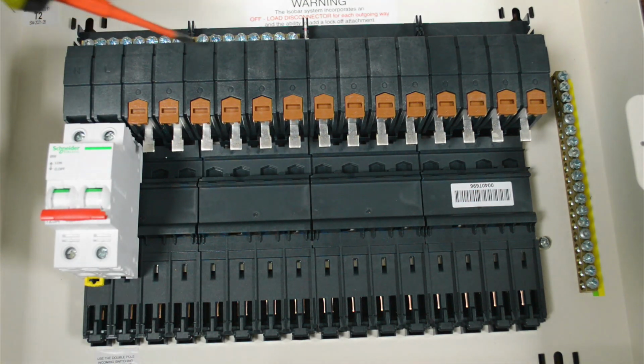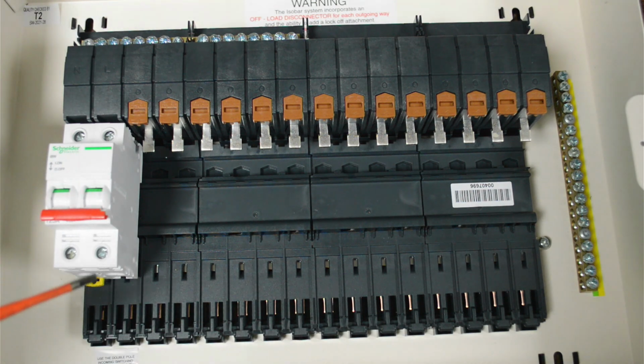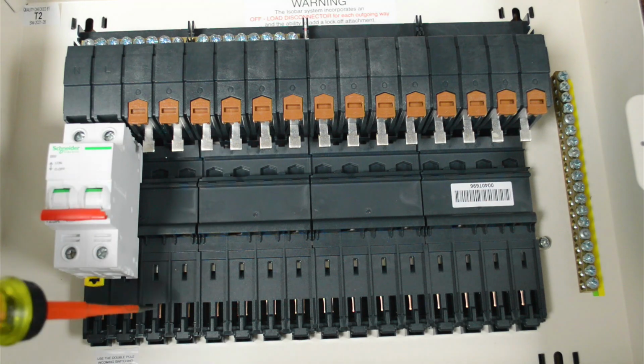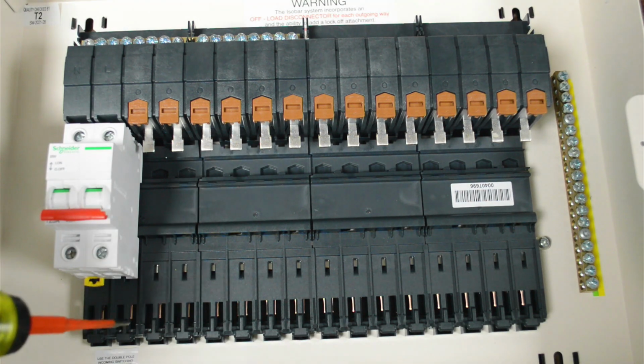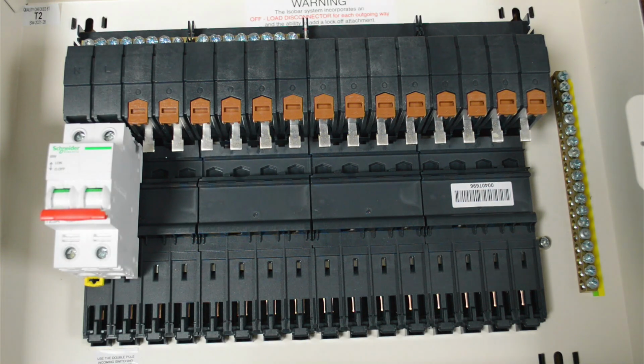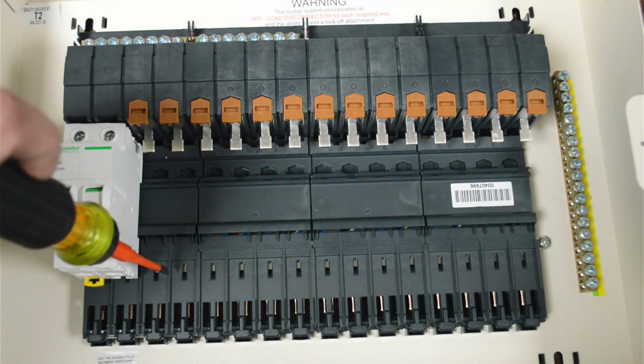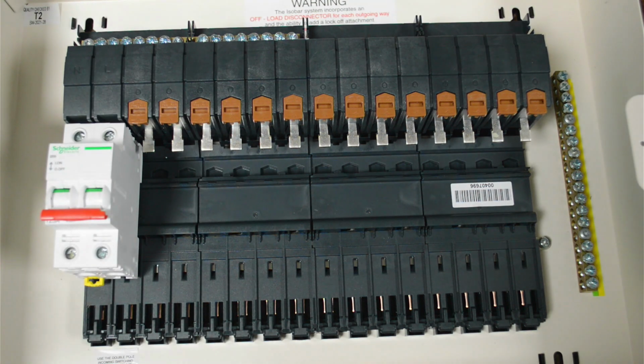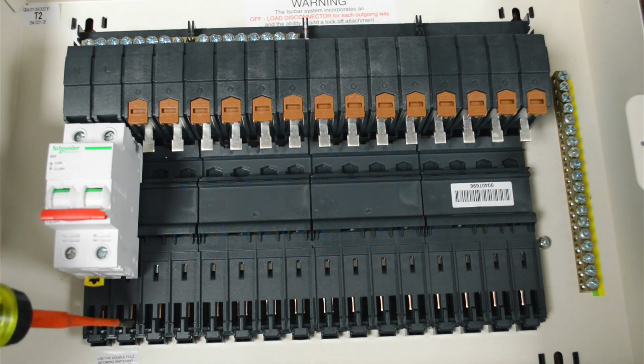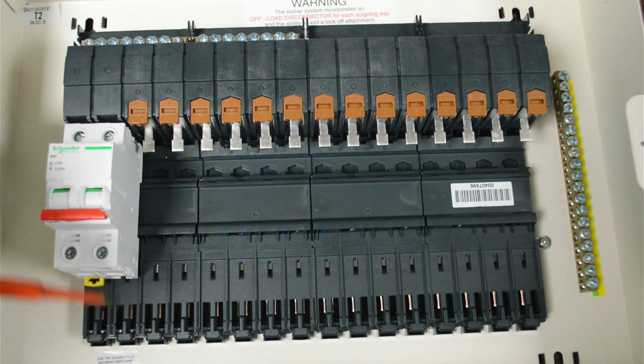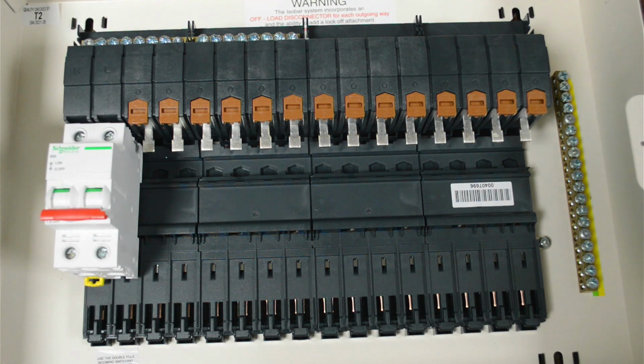Now there is also an earth bar over here and a neutral bar up here as well. But the beauty of these is you can actually use an RCBO that would clip in to this system to provide its connection to both earth and neutral. And if you see in here, you've got the little holes, and this hole there is where the earth pin on the back of an RCBO connects, and in here this is where the neutral would clamp around and effectively join into the neutral here. So in essence you have a line, a CPC and a neutral busbar, if you like, clip in clip out system, and I'll show you how that works in a minute.